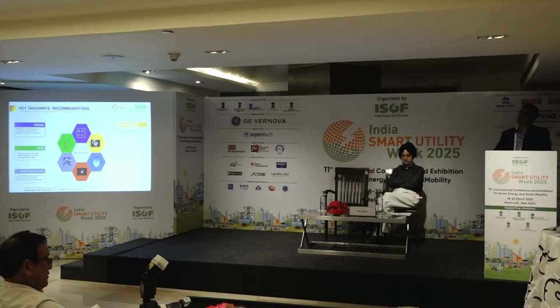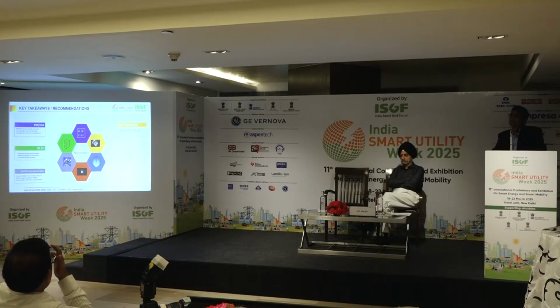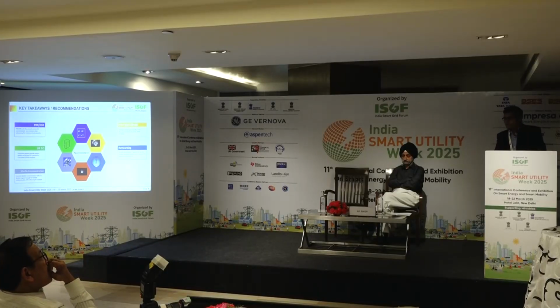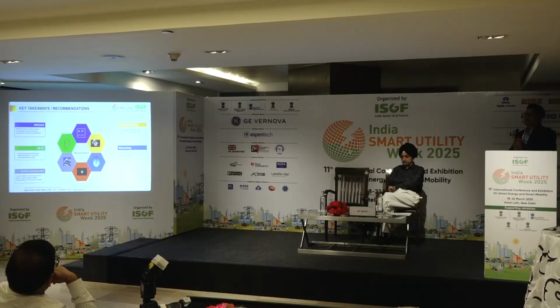PTP time server is very crucial for the digital substation. PTP is another costly one, but you need to have a redundant PTP server. If you go for a single PTP server and it fails, your complete protection will be jeopardized and you cannot use the substation. Only overcurrent and earth fault protection will be available, no other protection will be available. As we can see, at the process bus level we are dealing with protection data.